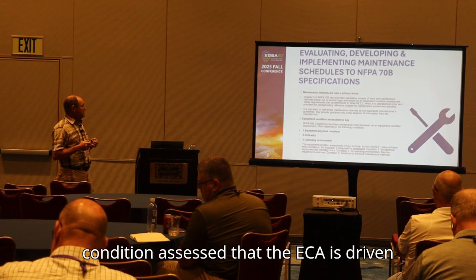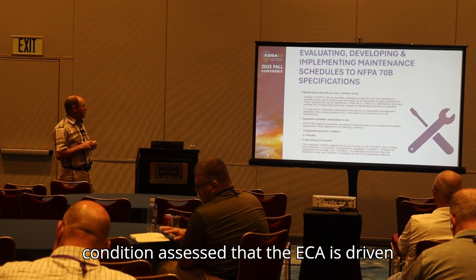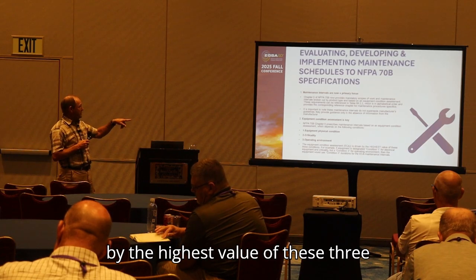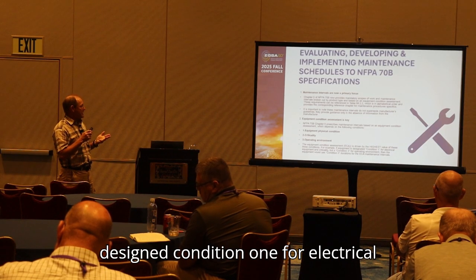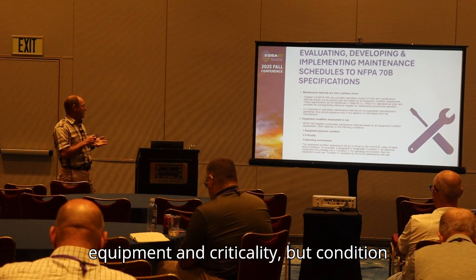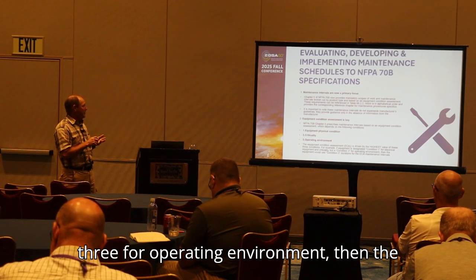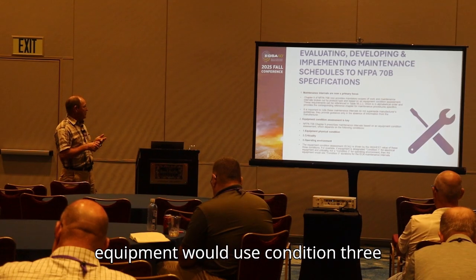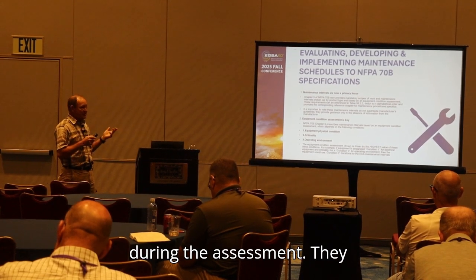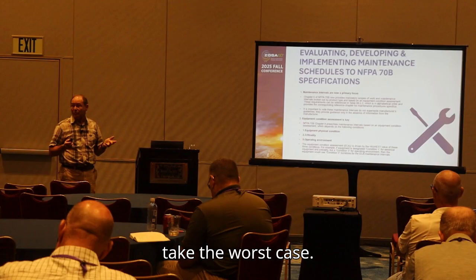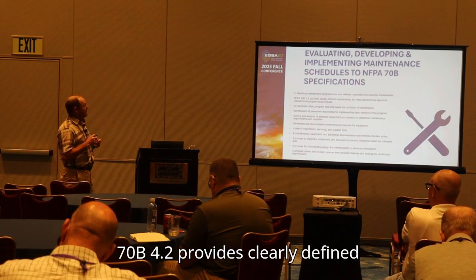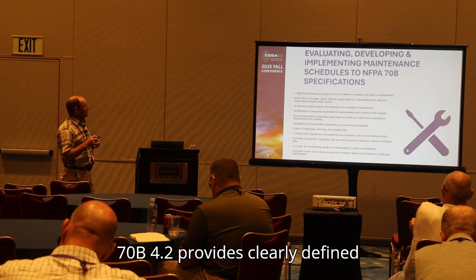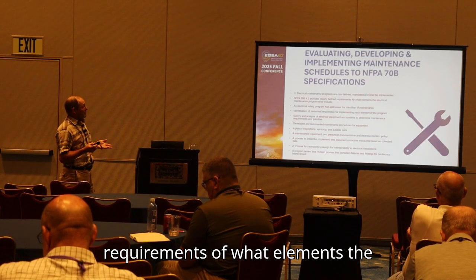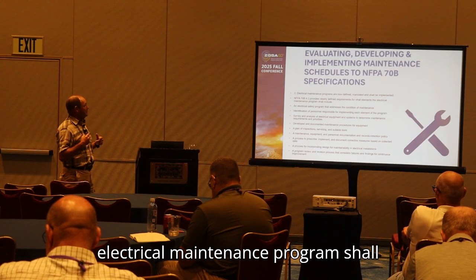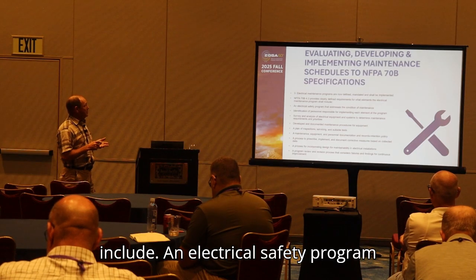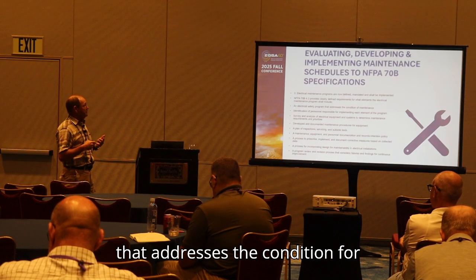The equipment condition assessed, the ECA, is driven by the highest value of these three conditions. For example, if equipment is designed condition 1 for electrical equipment and criticality, but condition 3 for operating environment, then the equipment would use condition 3 during the assessment. They take the worst case. 70B 4.2 provides clearly defined requirements of what elements the electrical maintenance program shall include. An electrical safety program that addresses the condition for maintenance.